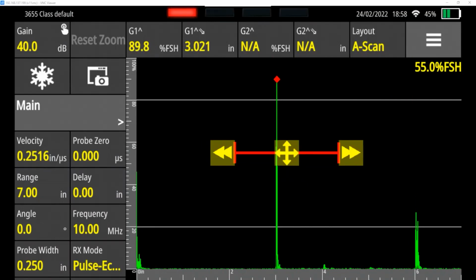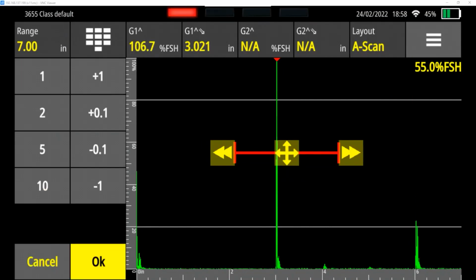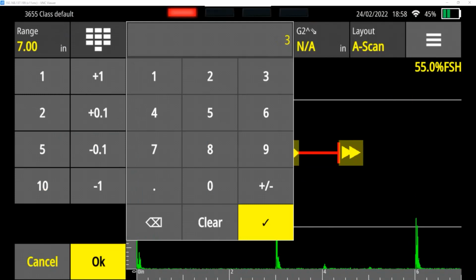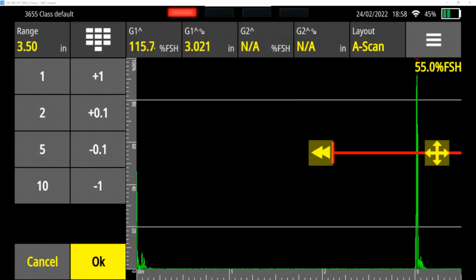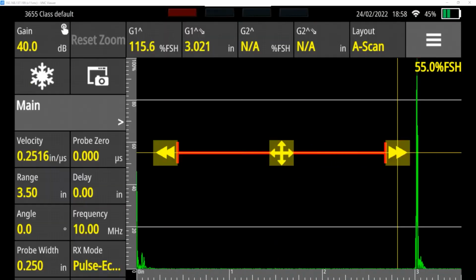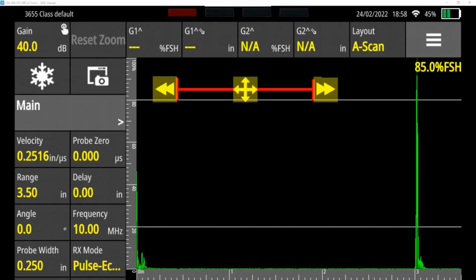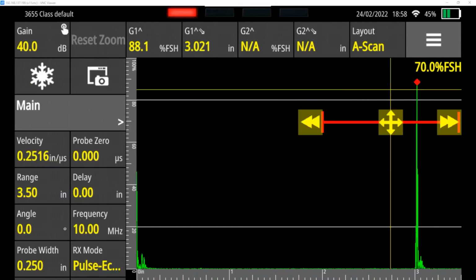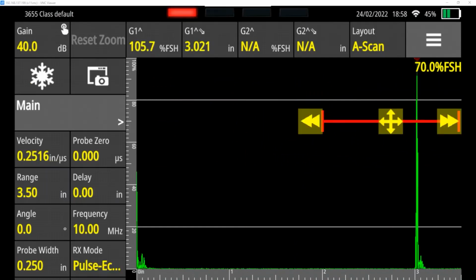Now we need to adjust our probe zero, but at this point we don't need that secondary echo anymore. So I'm going to go ahead and change my range. And remember, this block's only 3 inches thick. So I'm going to go to 3.5 inches. Okay. I can drag my gate over, kind of up out of the way. We don't need it from there. Okay. Actually, we do need it. Excuse me. So I'm going to put my gate over this. You can see we're at 3.021.